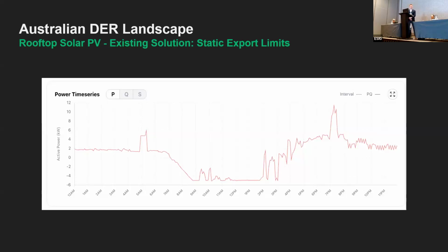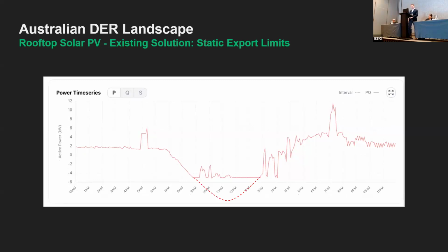This slide goes through the standard approach taken to date in an Australian context: introducing a static export limit at the customer level. That's a fairly dumb solution in the sense that it's local control and static. There's a clip-on CT typically put on the meter, limiting what the inverter can export at a fixed limit all the time. The dashed line shows the amount of foregone energy as a result—energy that could have been provided by that distributed resource but wasn't, because of this scheme being in place regardless of what's happening locally on the grid or at a macroscopic level.